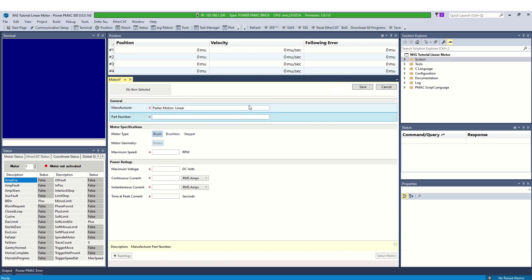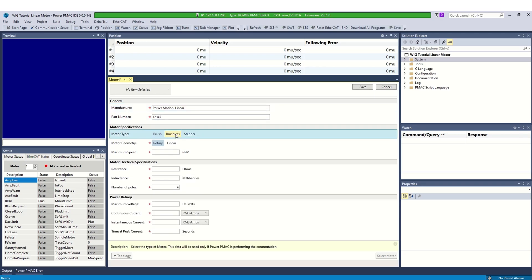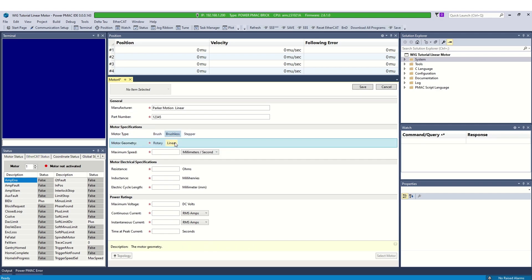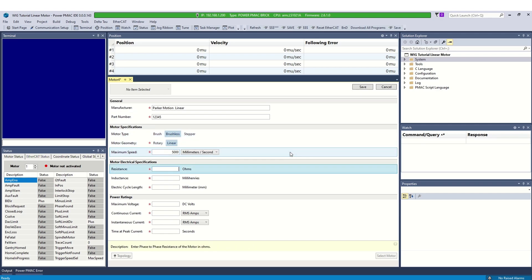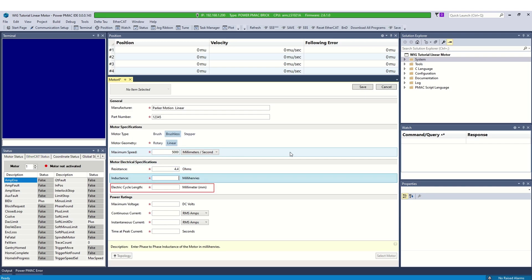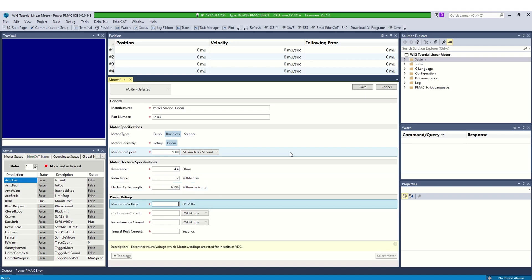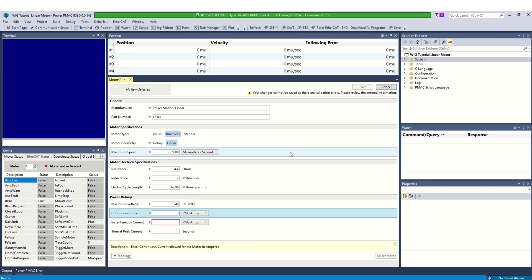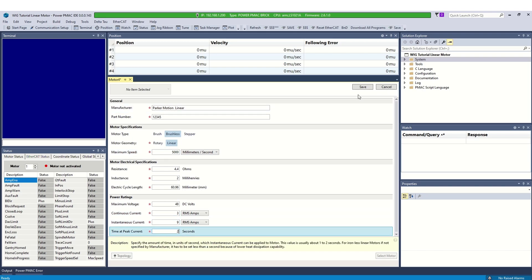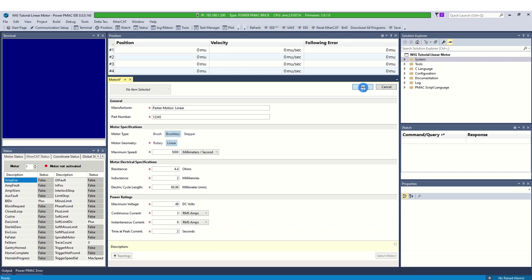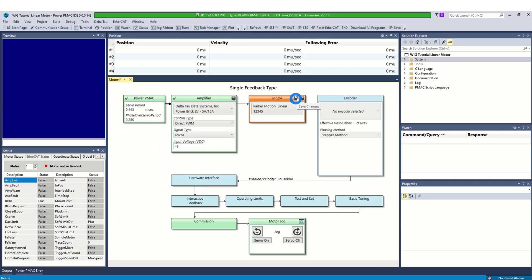In this example, we are using a linear brushless DC motor, so specify the motor type as brushless and geometry as linear. Enter the electrical specifications. Specify the correct electrical cycle length as it is very important in motor phasing. In power rating section, specify motor ratings. Click save for the database entry. Select the motor. Click save to save the selection.